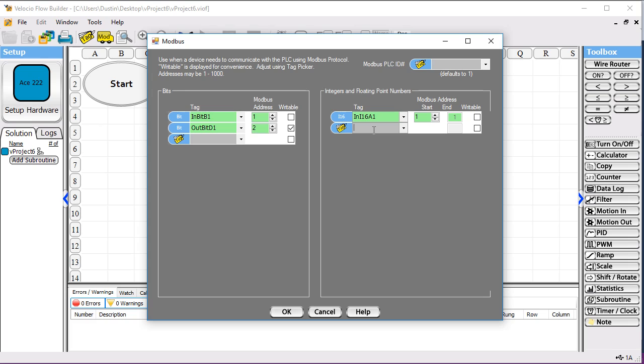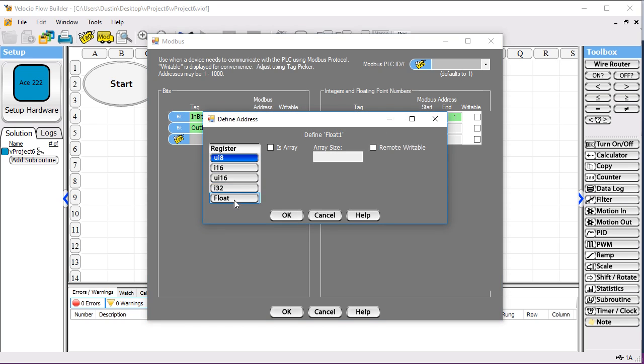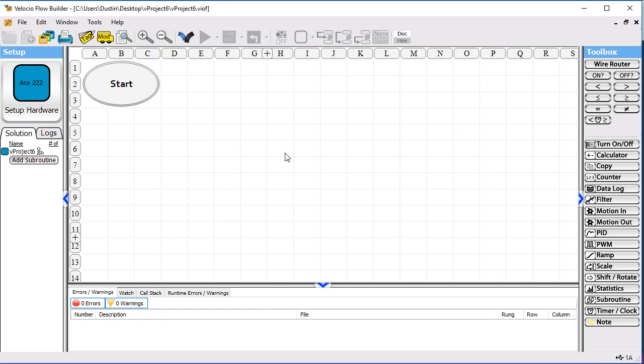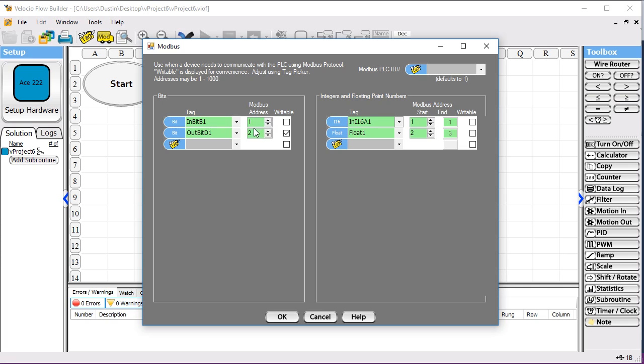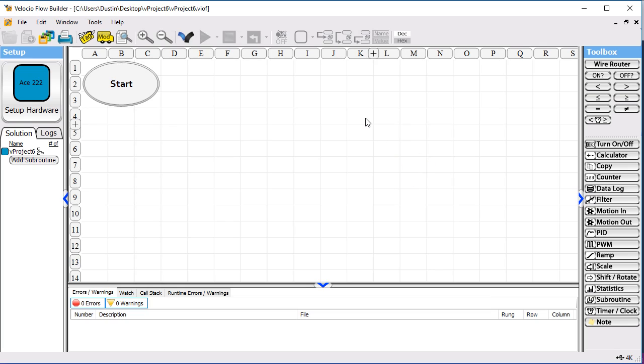We'll read in one of our analog inputs from this board. And we'll also create something just to have a different data type — we'll call it float1, and I'll define it as a float. Let me point out the addresses so you'll have them when you get further along in this example. The input bit was 1, the output was 2, the I-16 input was 1, and the floating point was addresses 2 and 3. We're going to need that in the next part of our example.